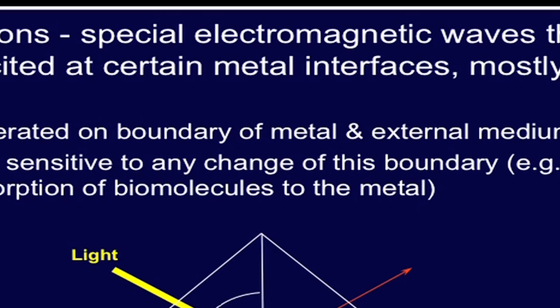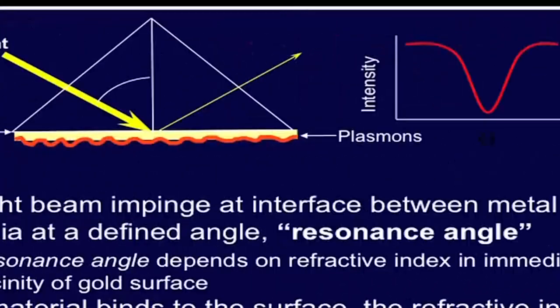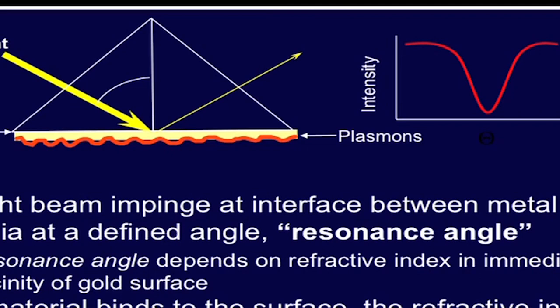From the gold surfaces, these plasmons are generated at the boundary of metal and external medium, which is usually air. They are very sensitive to any changes on this boundary, like adsorption of biomolecules to the metal. In SPR, a light beam impinges at the interface between metal and media at a defined angle called the resonance angle. The resonance angle depends upon the refractive index in the immediate vicinity of the gold surface. When a molecule binds to the gold surface, the refractive index increases and the SPR curve shifts toward higher angles. These changes in the angle of reflection of light, caused by the binding of probe to the immobilized proteins, are measured for the characterization of biomolecular interactions in real time.